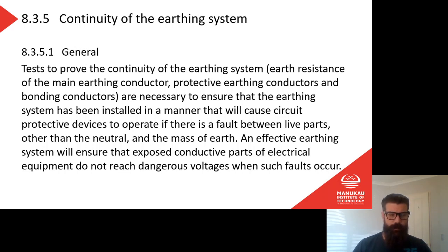It will be here literally all day. But the short answer is, as I said before, we need to test that all of the wires in the earth system are continuous and have a nice low resistance, because that's our primary protection system. It means that if a phase wire, a live wire, contacts any of my earth wires, it's going to cause a short circuit, and that should blow the circuit breaker. I want that to cause a short circuit, because that's going to trip the circuit breaker and therefore turn the supply off. So if any live conductors come in contact with anything I might touch, then it should cause a short circuit and blow the circuit breaker, which is a good thing.